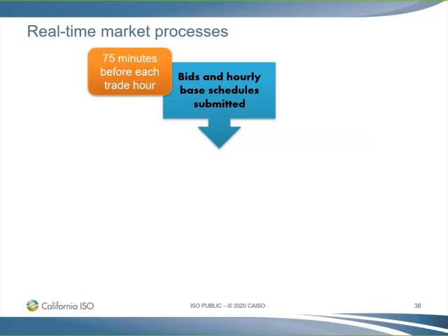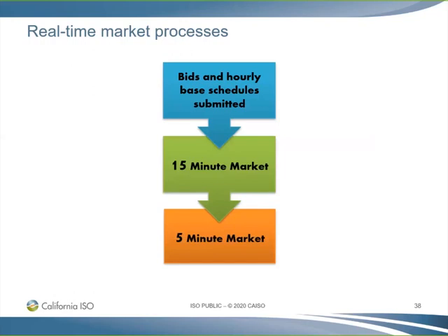As we move into the real-time market, at least 5 hours ahead, we look at our updated forecast and begin committing resources as necessary. From the time the day-ahead market schedules are posted to 75 minutes before the trade hour, bids can be submitted for the real-time market. We have an hour-ahead scheduling process for scheduling energy and ancillary services based on bids submitted by imports.